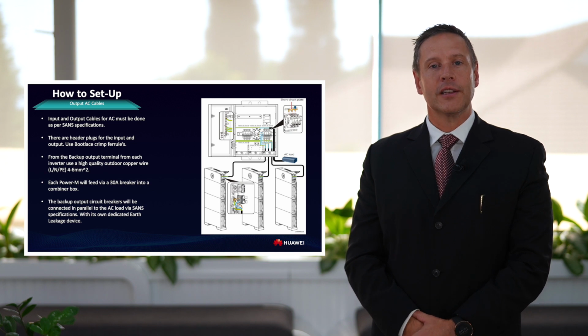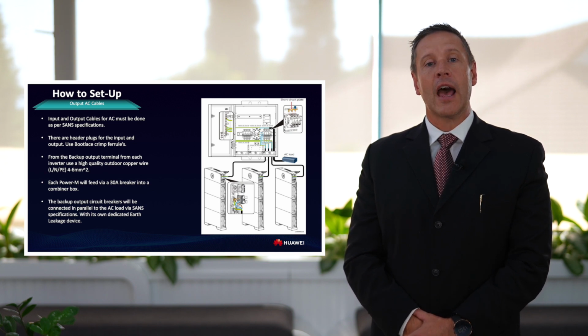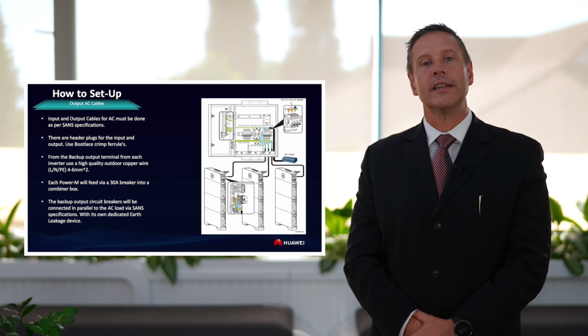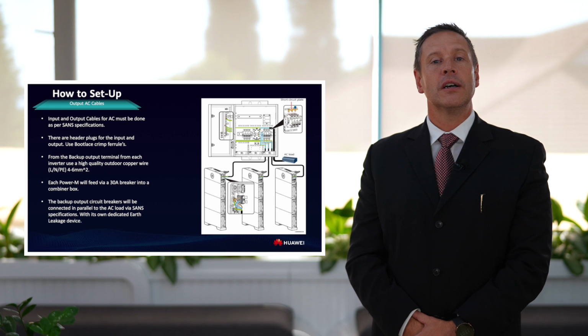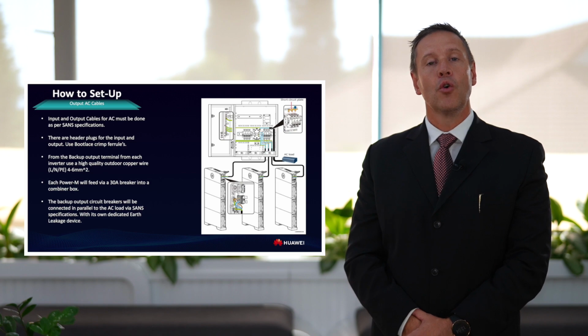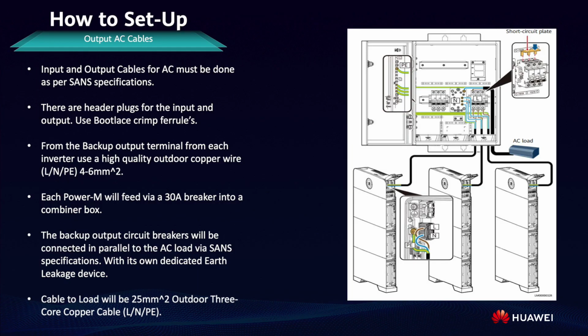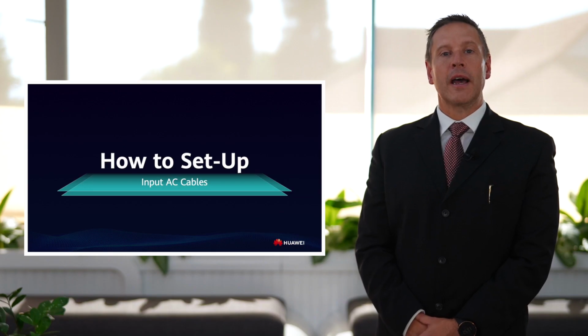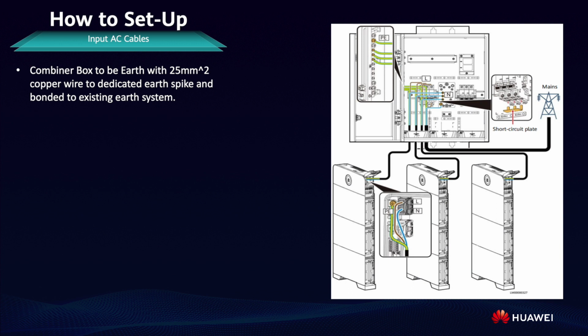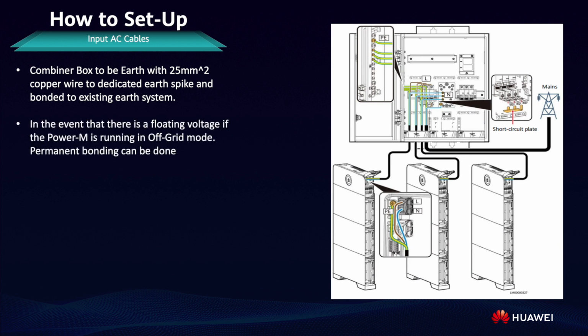Therefore, parallel connected power M devices can reach as high as 90 amps when connected in parallel. Therefore, the supply cable that will be supplying the power M as well as the output cable will be at least a 25 square millimeter high quality 3-core copper cable. Input cables from AC grid, utility side. Combiner box to earth will be with at least a 25 square millimeter copper wire with a dedicated earth spike and bonded to the existing earth system. In the event that there is a floating voltage, the power M can be permanently bonded to ground.